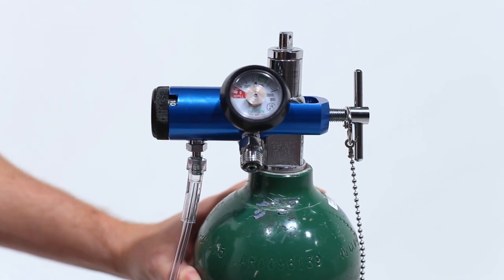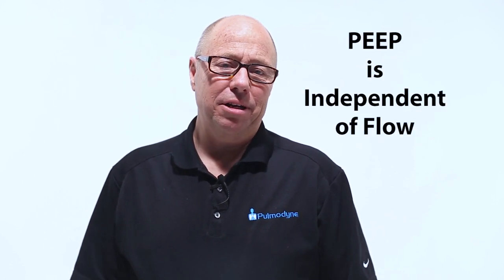So by now you're probably thinking, you really haven't told me anything that makes this different than what I'm currently using. Well, here you go. It simply connects to the low-pressure barb. You turn it to 10 liters per minute. You do not exceed 10 liters per minute. You set the PEEP and let it work. The PEEP is independent of the flow. You never have to adjust the flow to increase or decrease the PEEP pressure, which is the case in other devices.